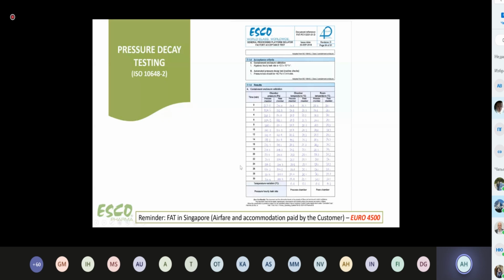And for isolators, it's very common for the customer to want to come to the factory to actually do FAT. But nowadays in COVID-19, it's very difficult to do so. So a lot of this factory acceptance test is done online via a Zoom video conference. Now, excluding the airfare and accommodation, an FAT process will cost about 4,500 euros. Pressure decay testing follows this particular standard. All of this acceptance criteria comes from ISO 10648-2.